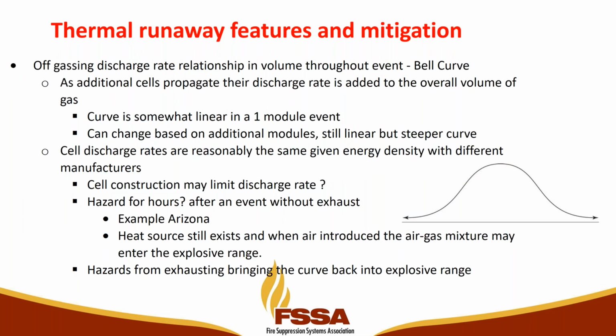The off-gassing discharge changes, as we said, somewhat like a bell curve. A single cell is probably fairly linear, but changes in the modules can change the steepness of that curve. Given reasonable energy density, the failure and gas production will be somewhat similar, but the construction of the module may limit that. How long does the event go on? Do you have any exhaust? Obviously Arizona was about four hours before there was an explosion.